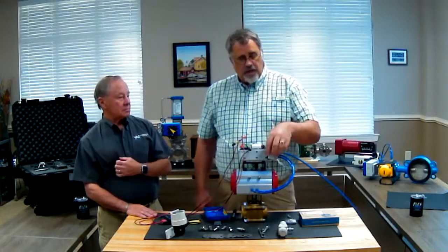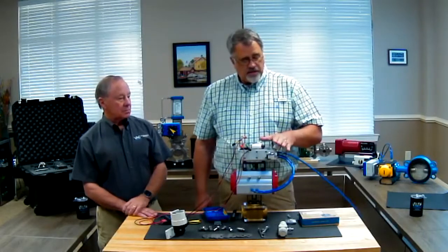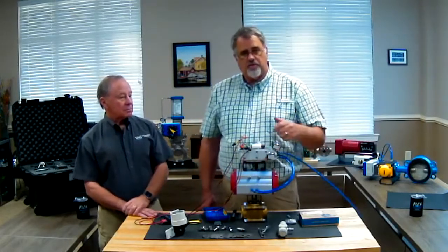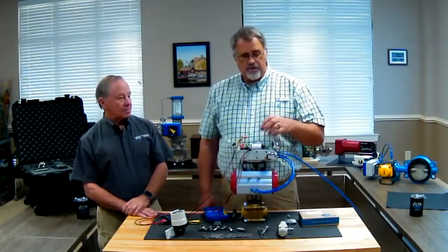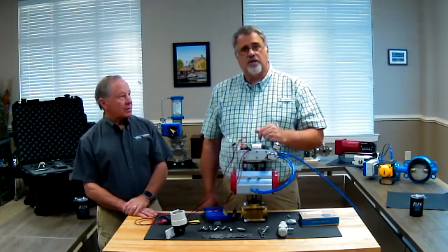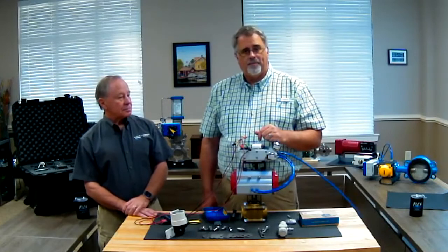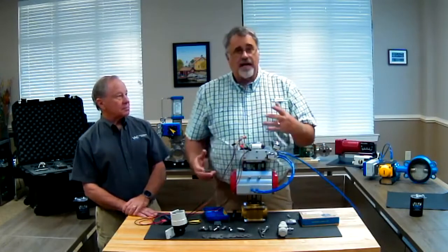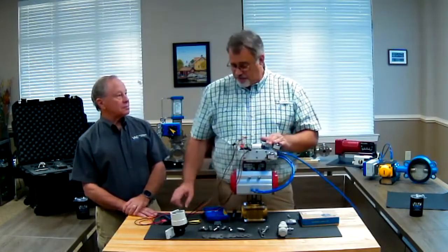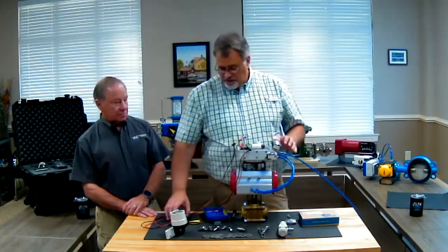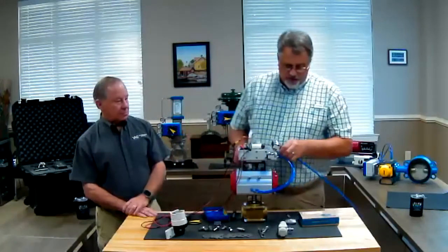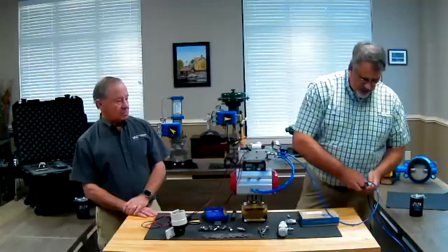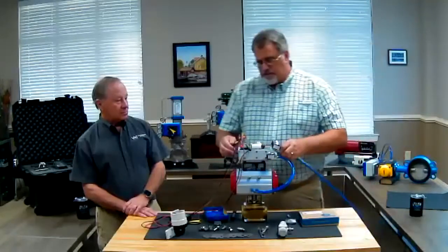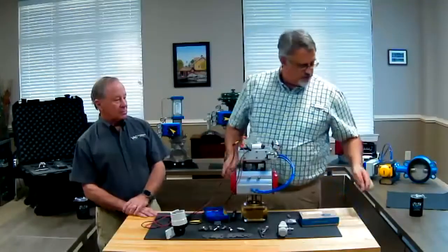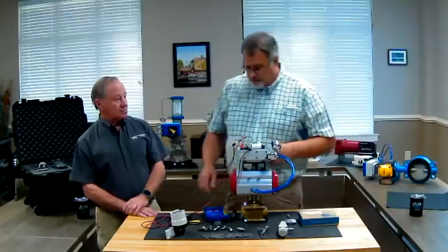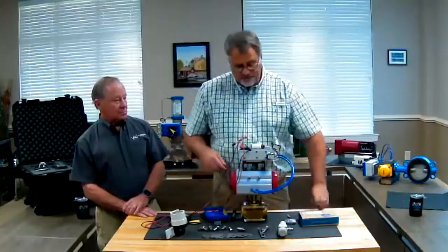So with one gauge, again, these gauges help you with calibration. This gauge helps you with troubleshooting. You can actually demonstrate to your customer how easy it is to work on this positioner. Now, this is not ragingly difficult. So we're going to actually turn this off now and air this down. And I'm going to show you how easy it is to take the I to P and the pilot valve out.